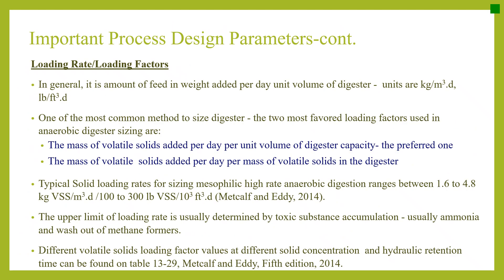Loading rate, or loading factor, is the amount of feed in weight added per day per unit volume of digester, with units of kg per cubic metre per day or pounds per cubic feet per day. It is one of the most common methods to size a digester. The two most common loading factors are: the mass of volatile solids added per day per unit volume of digester capacity (the preferred one for sizing), and the mass of volatile solids added per day per mass of volatile solids in the digester. Typical solid loading rates for mesophilic high-rate digesters range between 1.6 to 4.8 kg VSS per cubic metre per day.